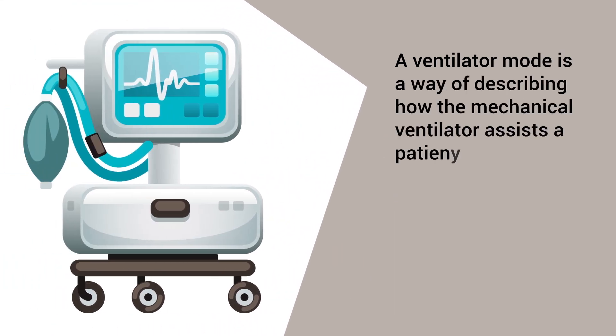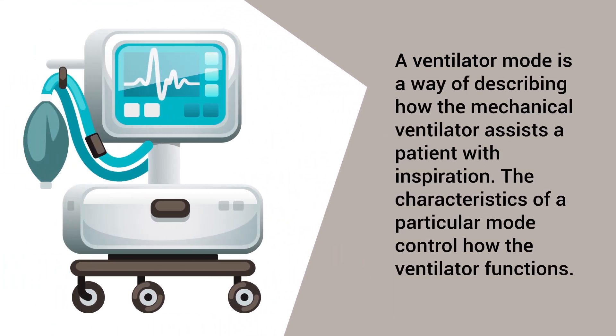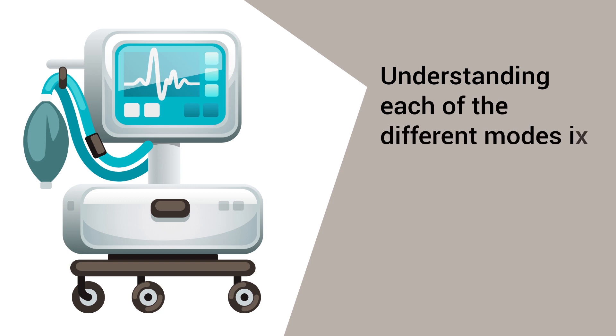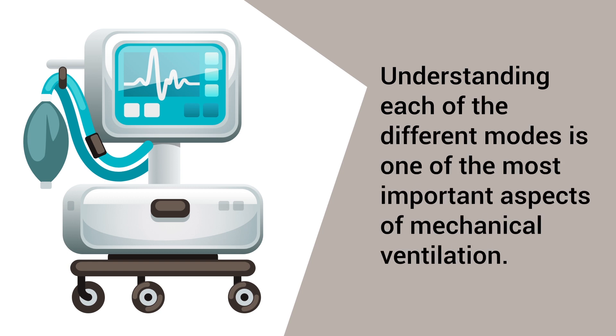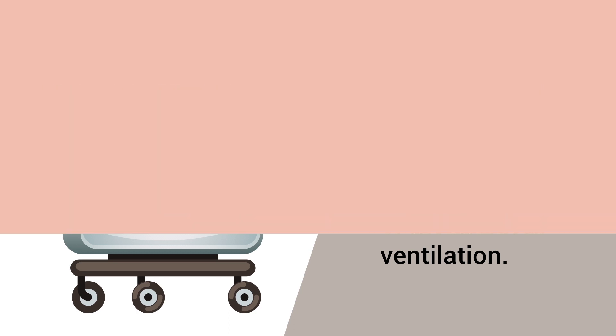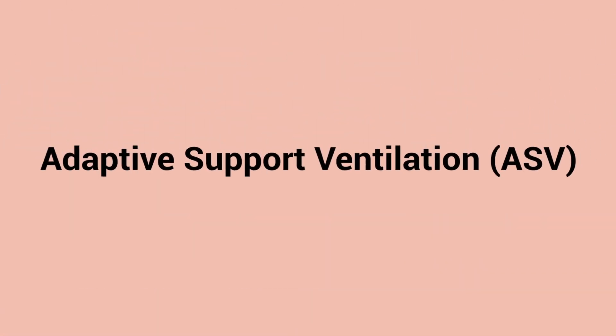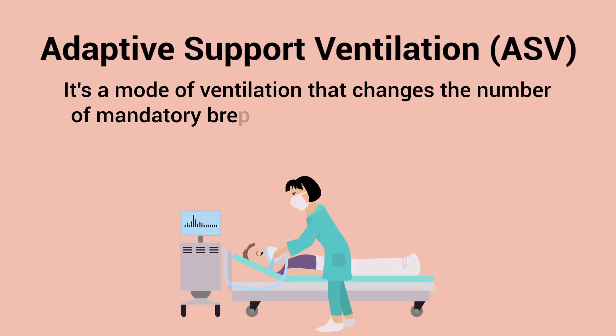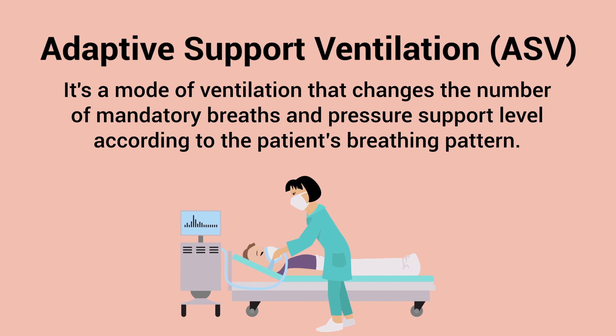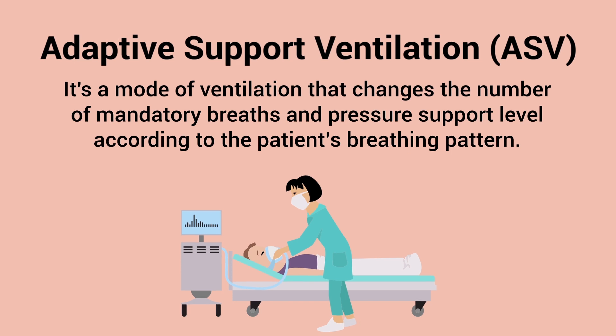A ventilator mode is a way of describing how the mechanical ventilator assists a patient with inspiration. The characteristics of a particular mode control how the ventilator functions. Understanding each of the different modes is one of the most important aspects of mechanical ventilation. One mode that is often overlooked is adaptive support ventilation, or ASV — a mode that changes the number of mandatory breaths and pressure support level according to the patient's breathing pattern.